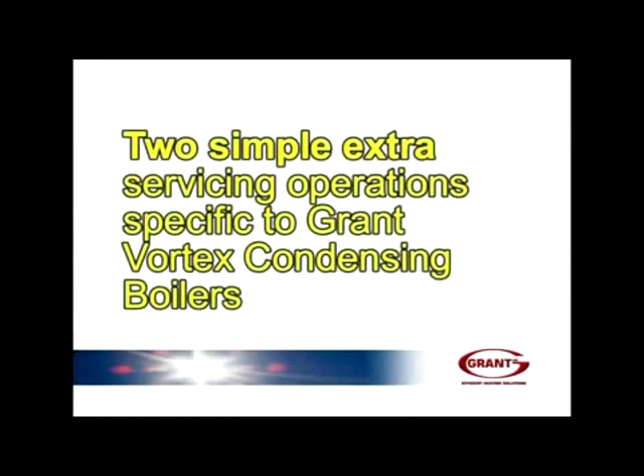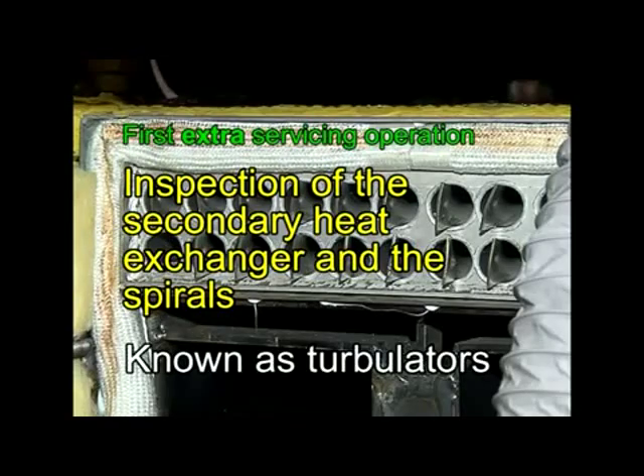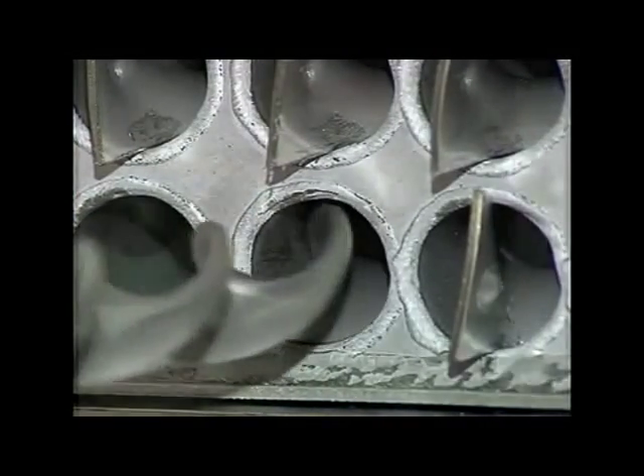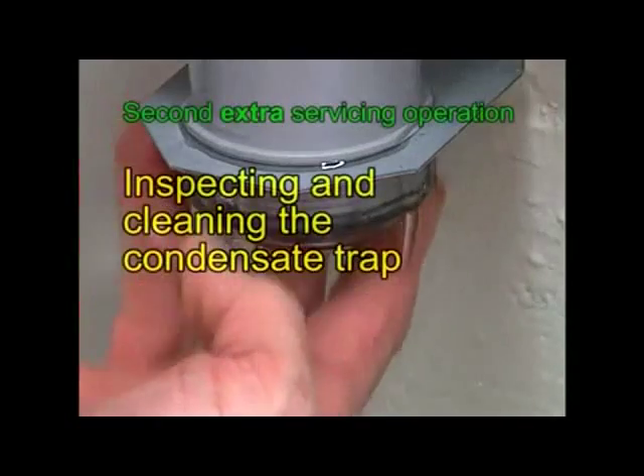Now to the two simple extra servicing operations that are specific for Grant Vortex condensing boilers. The first is inspection of the secondary heat exchanger and the spirals, known as turbulators. These you take out — often small pliers can help — inspect, clean and then replace. The tube should also be cleaned.